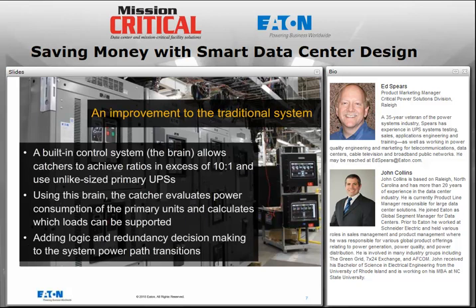So on the slide here, we offer some features that we'd like to see as an improvement to the traditional catcher type system. First of all, some built-in controls that will be redundant, and we'll call them the brain for the purposes of this discussion, but something that would allow the catchers to increase the number of primary UPSs that it can support. For example, instead of having one catcher serve 3 primary UPSs maximum, I'd like to be able to take care of up to 10 primary UPSs. That would be a lot better usage of the upfront expense and floor space and maintenance and all those kind of things. So the brain of the catcher system could evaluate the power consumption of each of the primary units and decide which loads can be supported by the catcher at any instant.